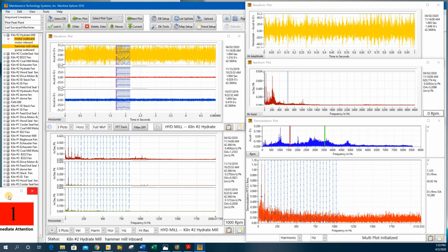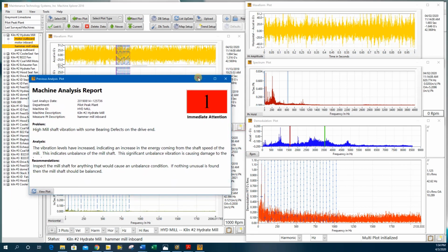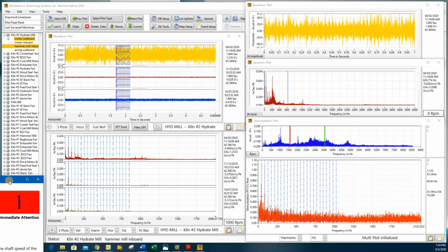Note that we had an immediate attention on this guy back in August. There's some things we certainly want to talk about. It's certainly still an immediate attention kind of vibration level here. This is the plot I'm going to show to our customer. So I click on our report button right here.